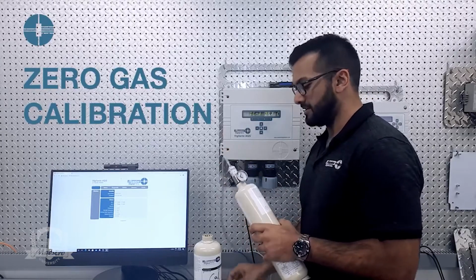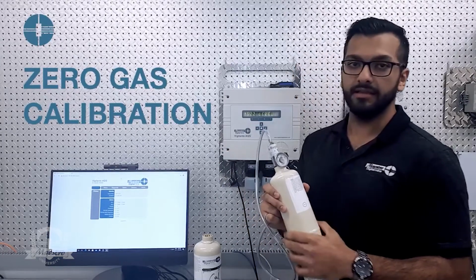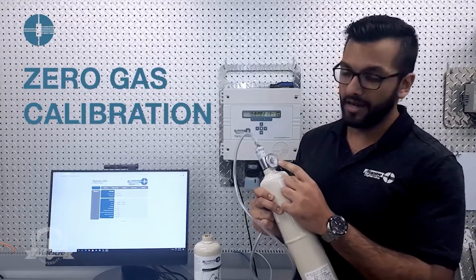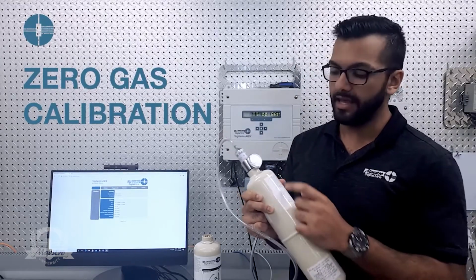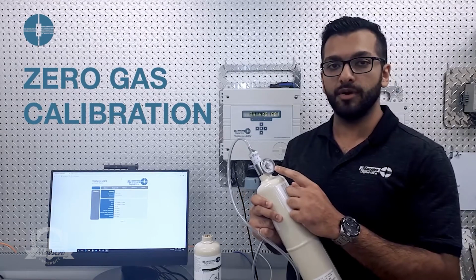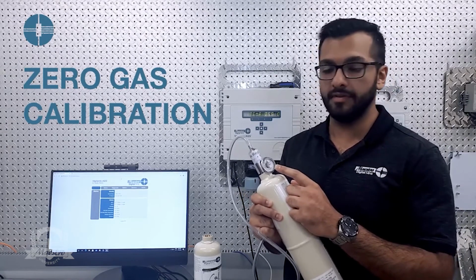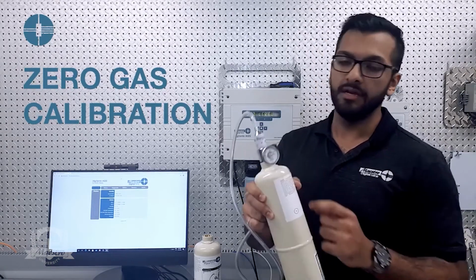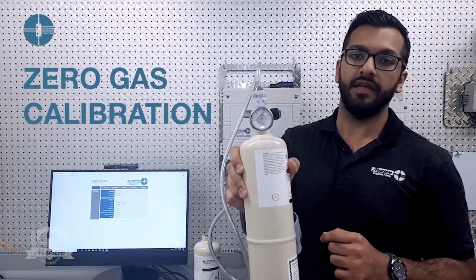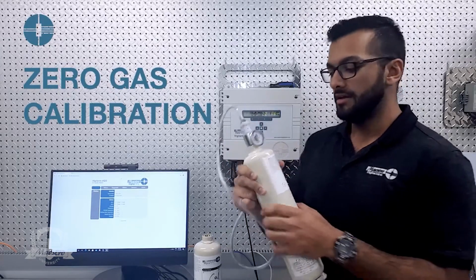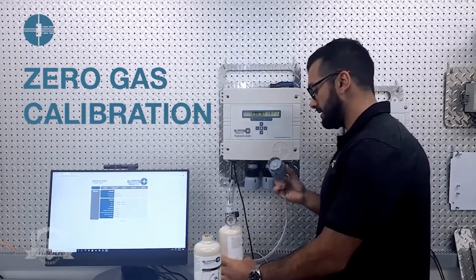And obviously you have to make sure that there is gas in the bottle as well. The regulator that Maestro provides has a gauge on it to show you the amount of pressure, which relates to how much gas is left in the cylinder as well. So you can see here, there is enough gas in this to calibrate the sensor. So we're going to start with zero gas.